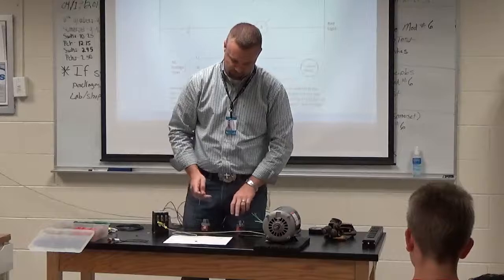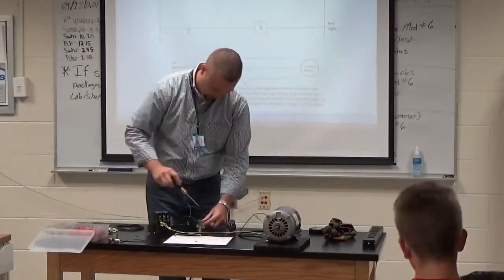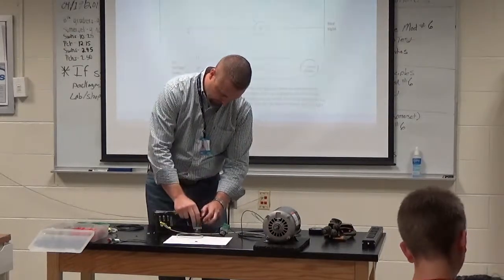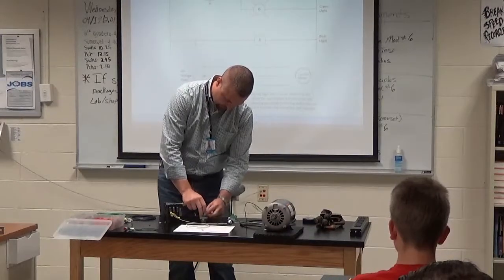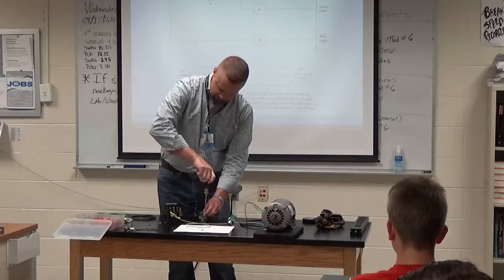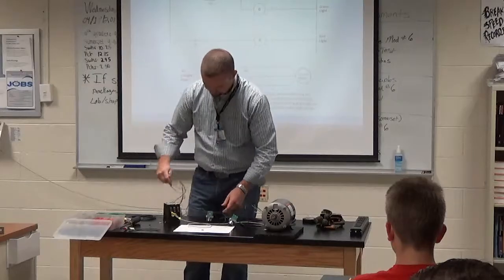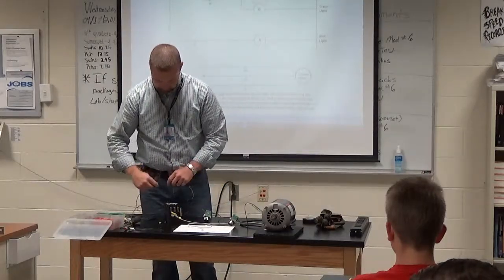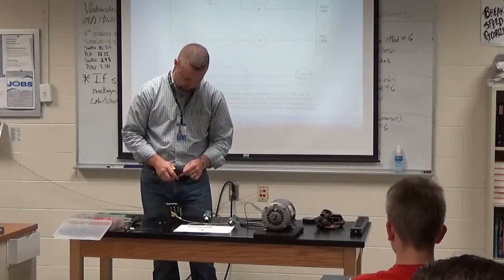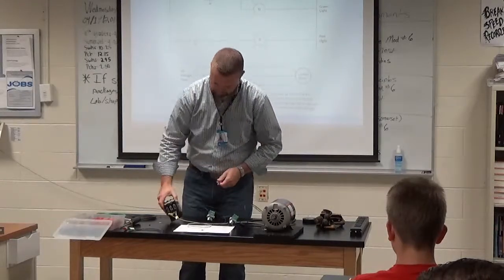So the wire in between the stop and start is the one I must connect to, okay, on my holding circuit. So I'm going to loosen the screw, insert my wire under that, hold it securely, tighten it down. Now, for this holding circuit to work efficiently, where must it go? Where does this wire need to go? What do you guys think? To the auxiliary contact on the motor starter. Good, Travis. Yes, it goes to the auxiliary contact on the side of the motor starter.